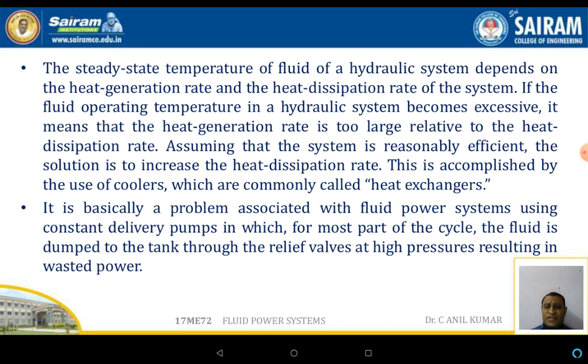Excessive heating accelerates oxidation and causes the oil to thin — that is, viscosity decreases — promoting deterioration of seals, packing, and wear between closely fitted parts such as valves, pumps, and actuators. The steady-state temperature depends on the heat generation rate versus the heat dissipation rate. If the operating temperature becomes excessive, the solution is to increase the heat dissipation rate using a cooler or heat exchanger. This is a common problem in systems using constant delivery pumps where fluid is dumped through a relief valve at high pressure, resulting in wasted power.